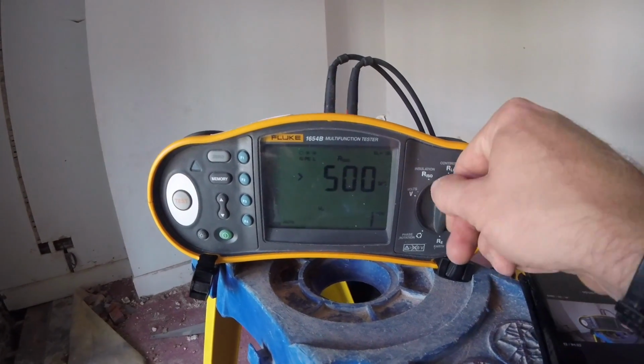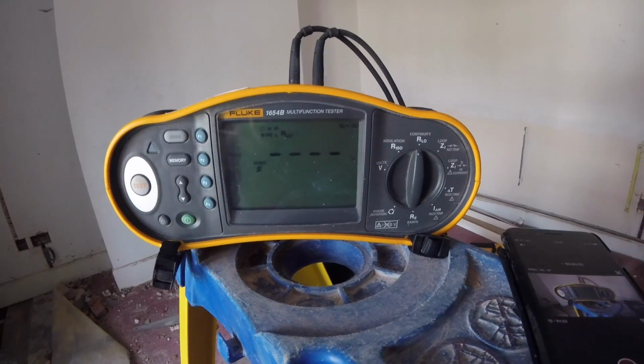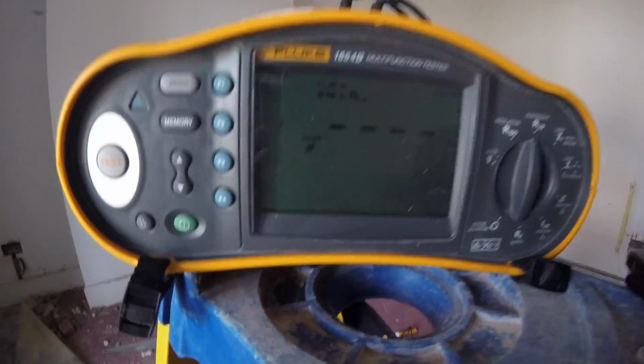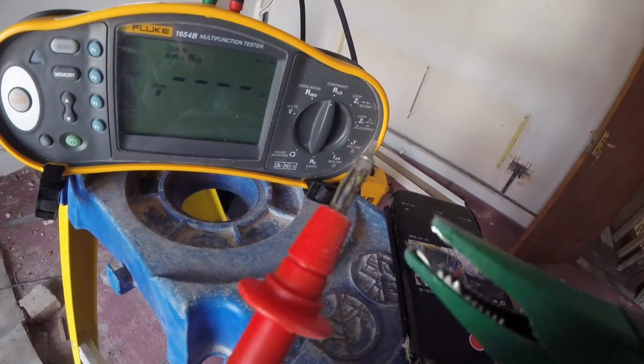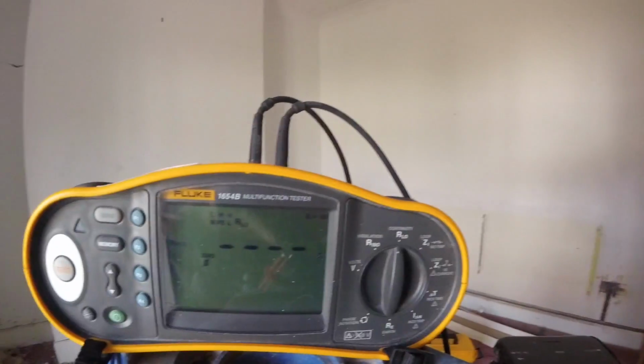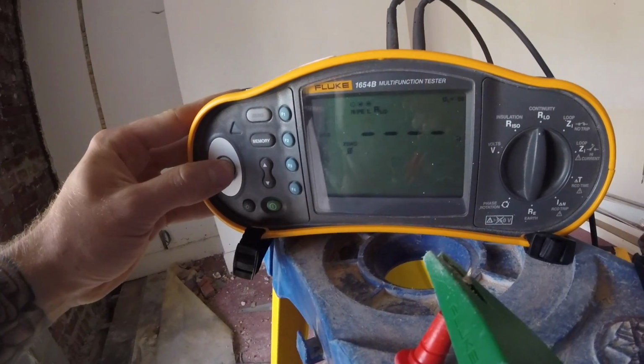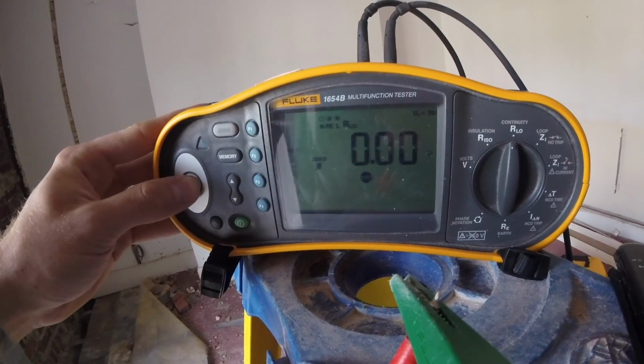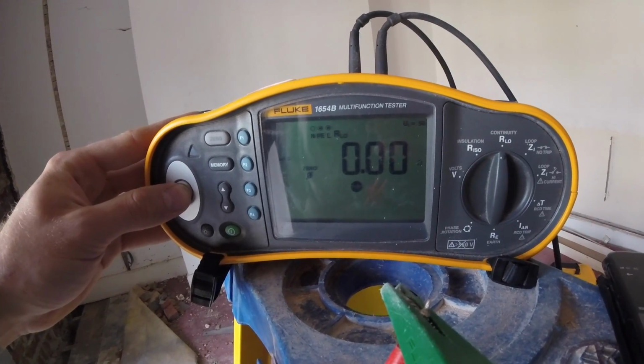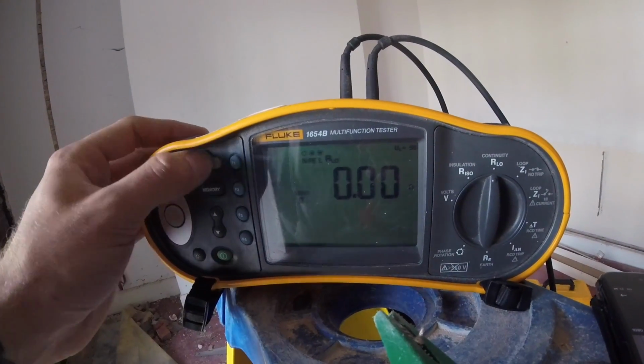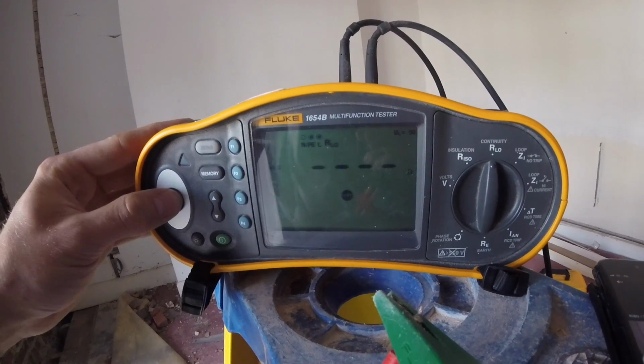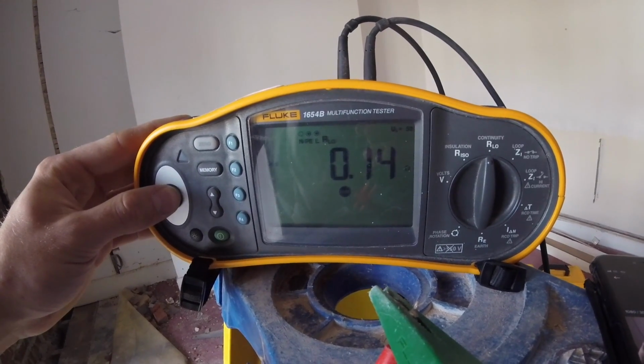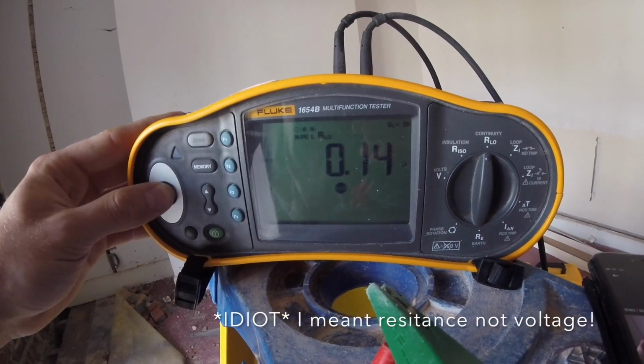So right, next test is continuity, is what it is basically. It literally just measures continuity, again obviously same two leads, red and green. If I put that clip on there and hold down test, that should measure the resistance of them leads, which is 0.00, because I have already zeroed them. So if I take that zero off and then press test, the actual resistance of them leads is 0.14 ohms.